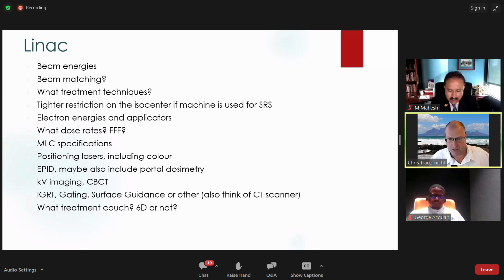Do you want an electronic portal imaging device for image or for positional verification? While you're at it, you might as well include portal dosimetry. May save you by purchasing a diode system if you still find those. Depending on the money, you may want KV imaging and cone beam CT attached to the LINAC. And then think about all the other stuff you want. Image guidance, gating, surface guidance. And this doesn't necessarily only apply to the new LINAC. You will need it on the CT scanner as well. What treatment couch do you want? Just the normal IGRT couch, or do you want the 6D couch? Again, there's a price difference with something you should think of, and all depends very much on the techniques you want to treat.